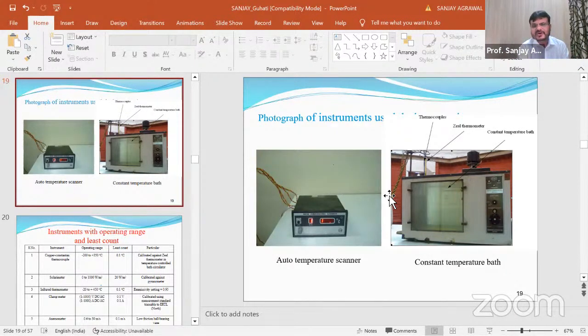Similarly, all these thermocouples are calibrated, and for calibration you need to take readings for approximately 24 hours, because you have to increase the temperature from ambient to 100 degrees centigrade, and then let it naturally come back from 100 degrees centigrade to ambient temperature.